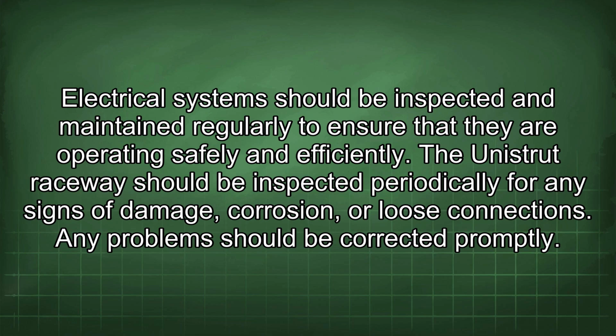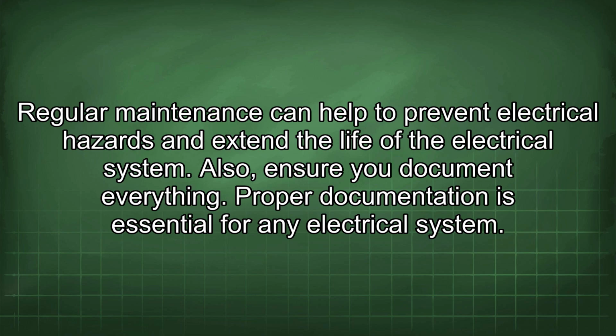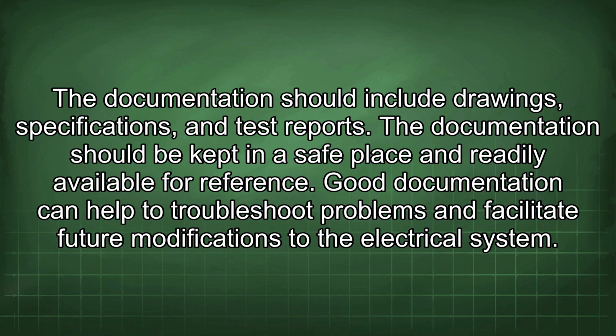The Unistrut Raceway should be inspected periodically for any signs of damage, corrosion, or loose connections. Any problems should be corrected promptly. Regular maintenance can help to prevent electrical hazards and extend the life of the electrical system. Also, ensure you document everything. Proper documentation is essential for any electrical system. The documentation should include drawings, specifications, and test reports. The documentation should be kept in a safe place and readily available for reference. Good documentation can help to troubleshoot problems and facilitate future modifications to the electrical system.